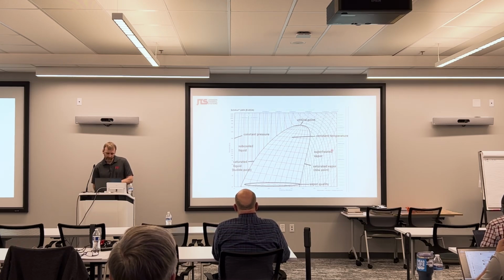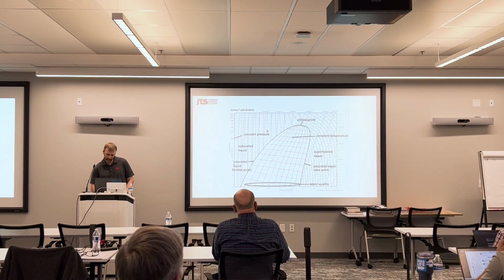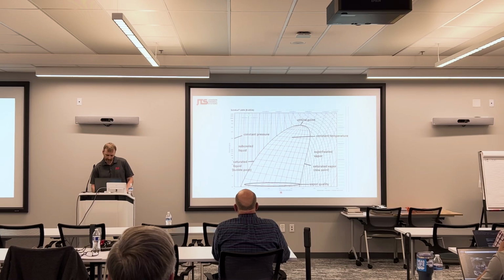To understand glide, we've got to understand the pressure enthalpy diagram, so I'm going to go over that real quick. On the Y scale you've got pressure, and on the X scale you've got enthalpy. This curve is known as your saturation dome, and everything underneath this curve is a mixture of liquid and vapor. Anything to the left side of this curve is subcooled liquid. Anything right on the edge of the curve is saturated liquid, your bubble point.